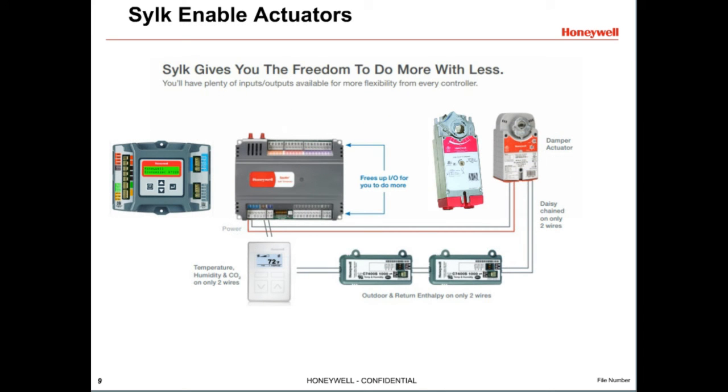Sylk is Honeywell's communicating bus. Sylk spring return actuators are compatible with any Sylk-enabled controllers, such as Jade Economizers and Spider controllers. Sylk is a two-wire, polarity-insensitive bus for communication between a Sylk-enabled controller and a Sylk-enabled actuator and other devices like sensors. With Sylk bus, you can daisy-chain Sylk devices, freeing up input-output points on the controller. The bus sends feedback from the actuator for early fault detection and diagnostics, including actuator cycle count. If the actuator is stalled, it even measures peak VA to warn of potential equipment issues.